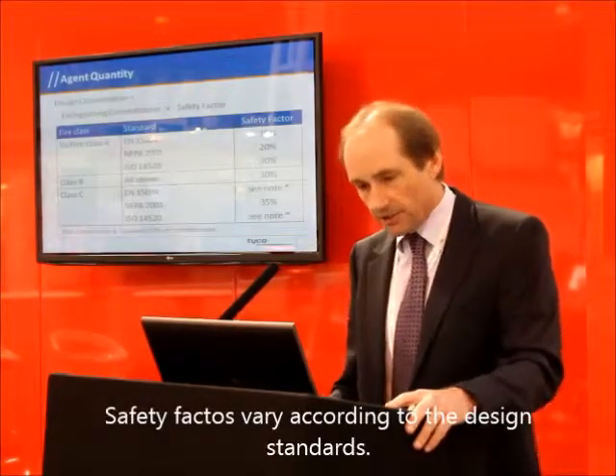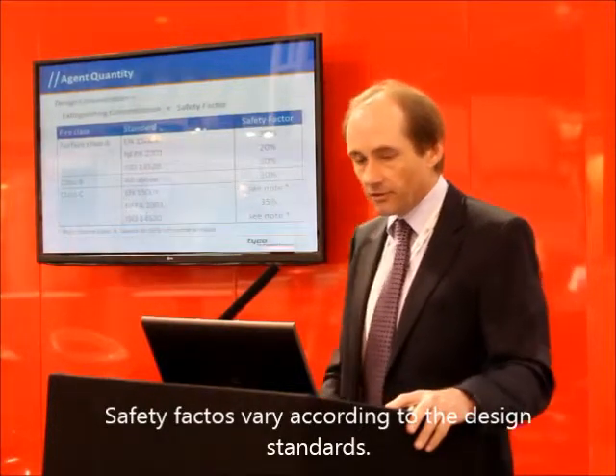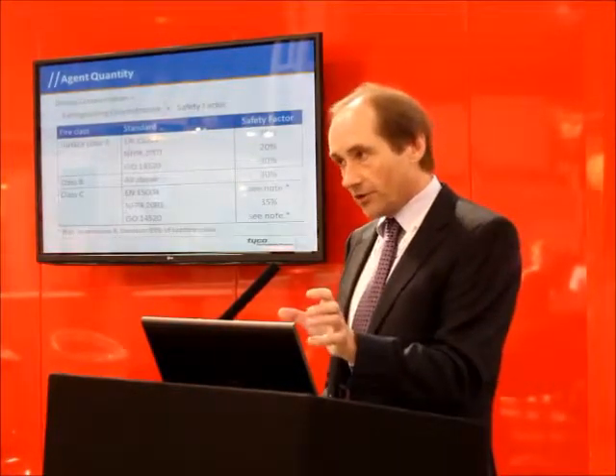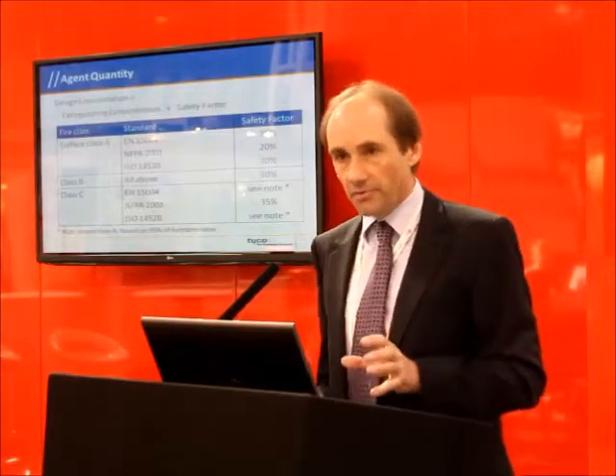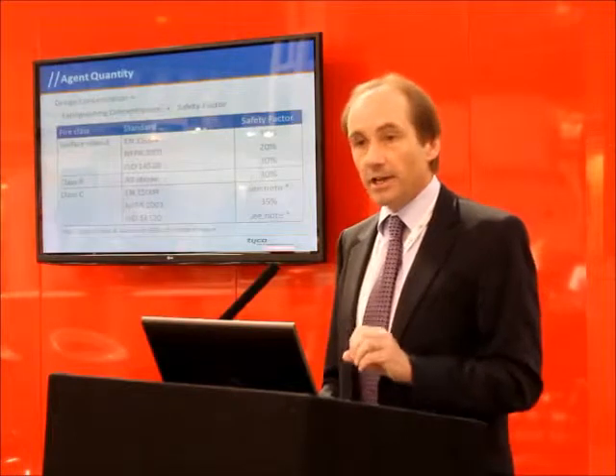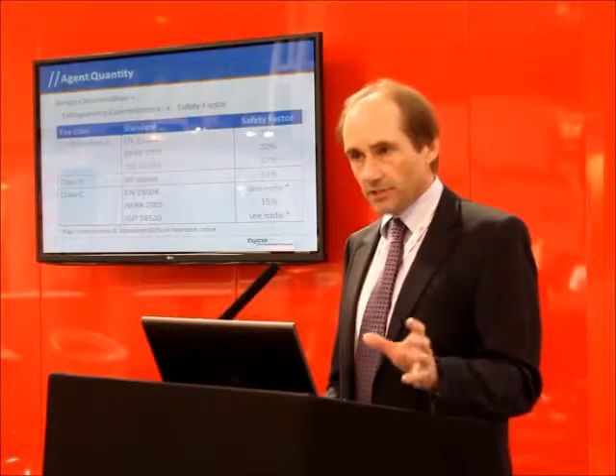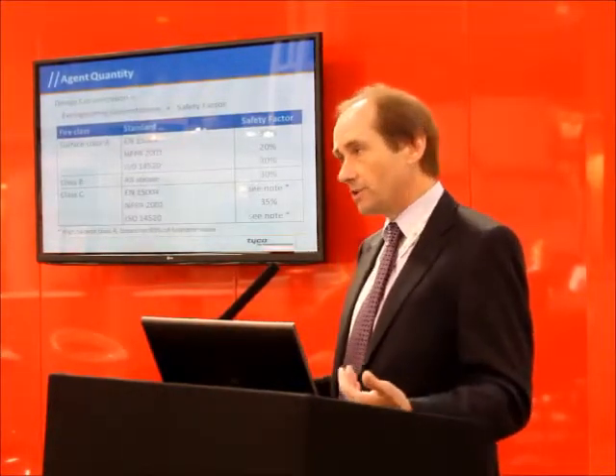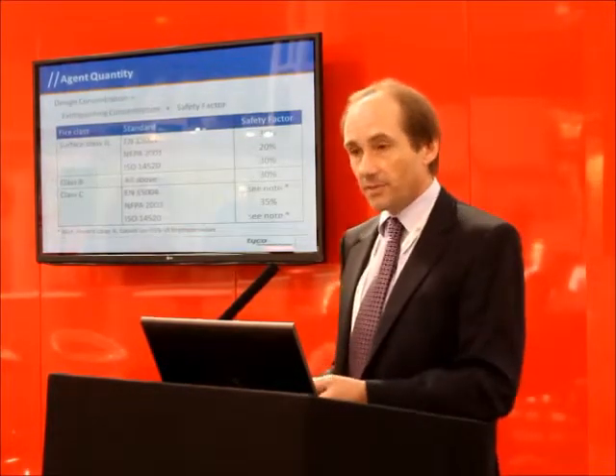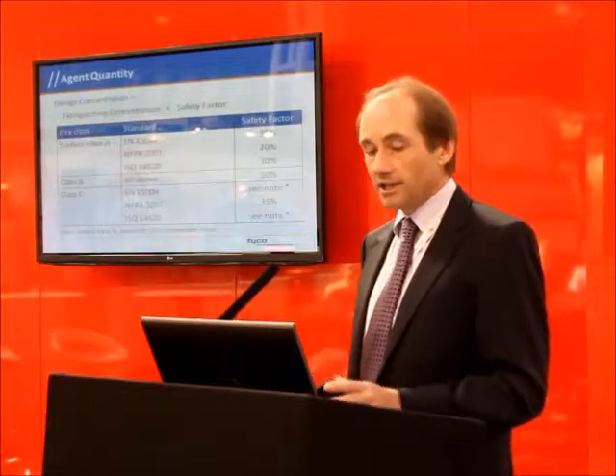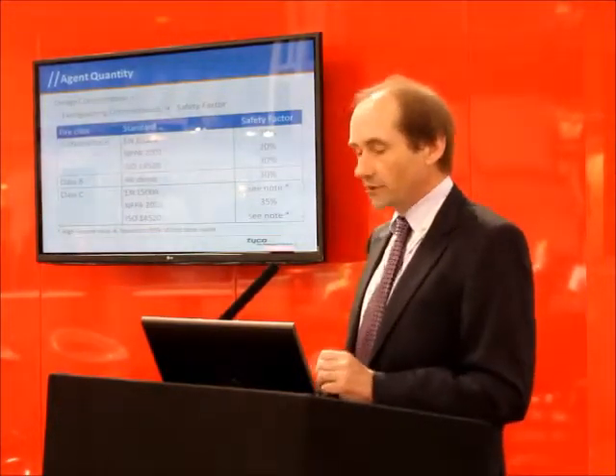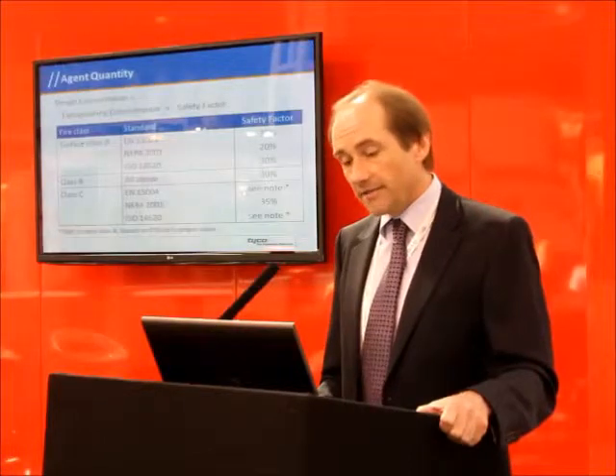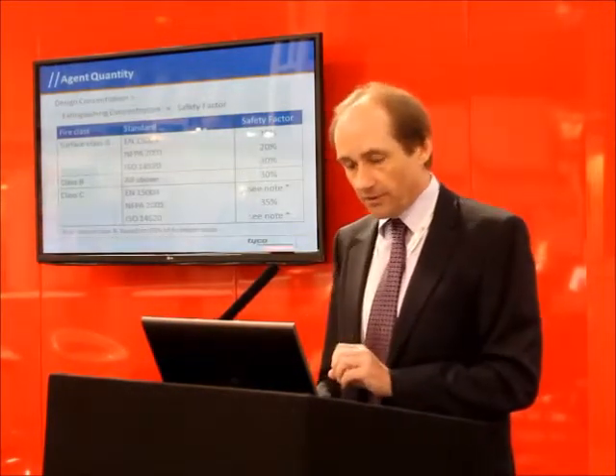So when we talk about the safety factors, the safety factors vary according to the design standards. A surface Class A fire under EN 15004 would require that you determine the extinguishing concentration and then apply a safety factor of 30% — that would get to your design concentration. NFPA 2001 looks at a similar method to determine the extinguishing concentration but then applies a reduced safety factor. So what actually happens is if you design a system according to EN 15004 compared with NFPA 2001, you will need more gas on the European system. ISO 14520 applies a 30% safety factor for Class A fires, in line with all of the standards.